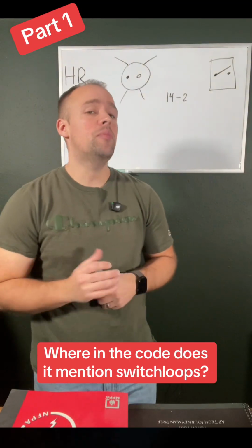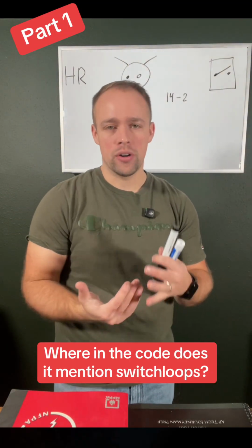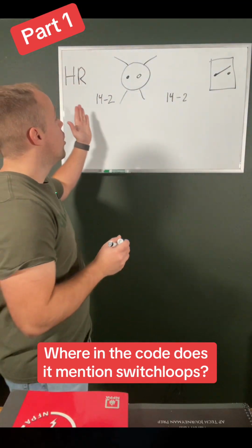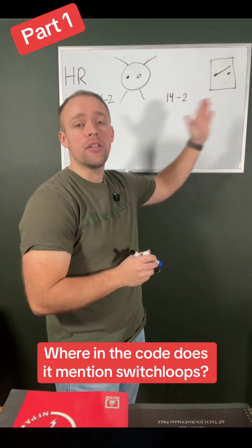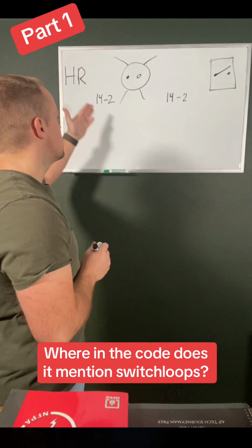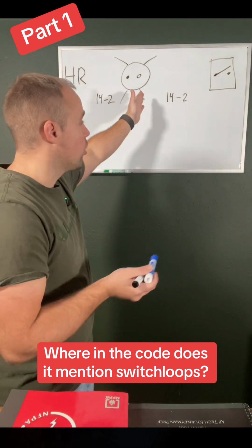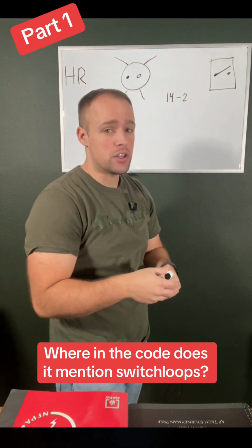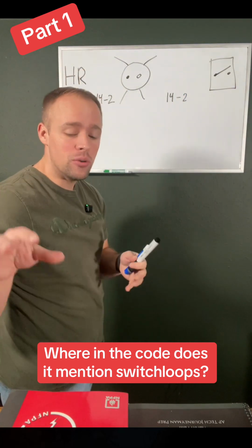Well, for a switch loop application, it's actually wired backwards, sort of, okay? So instead of the home run running directly to the switch and then to the light, a switch loop has the home run go to the light, or whatever the load is, then to the switch. And I'll show you how it is legal to do. It is in the code book.